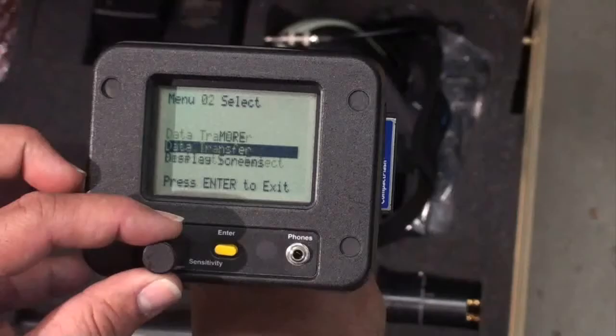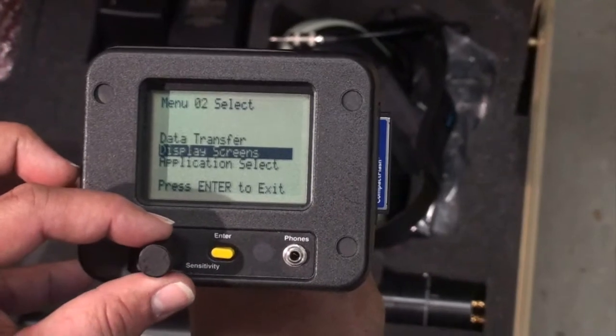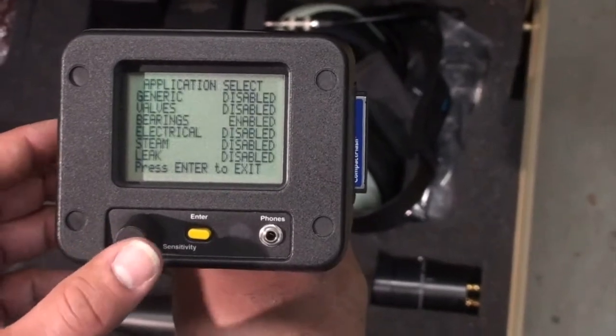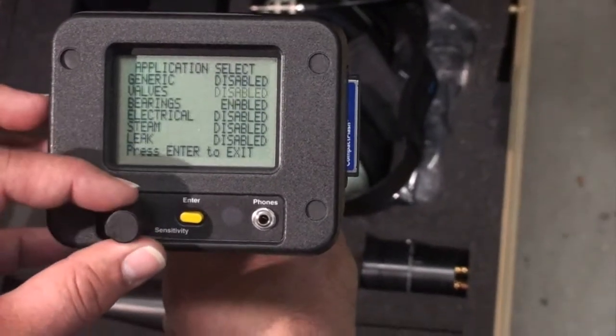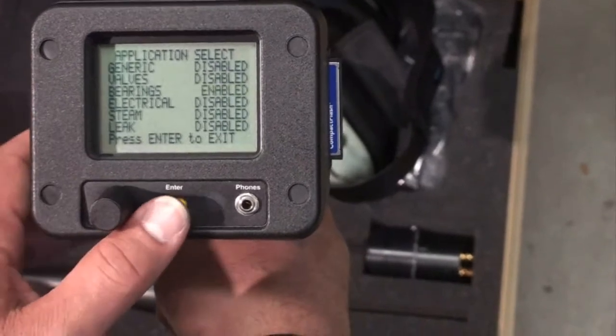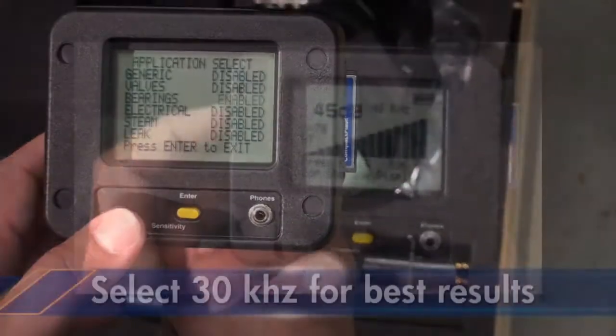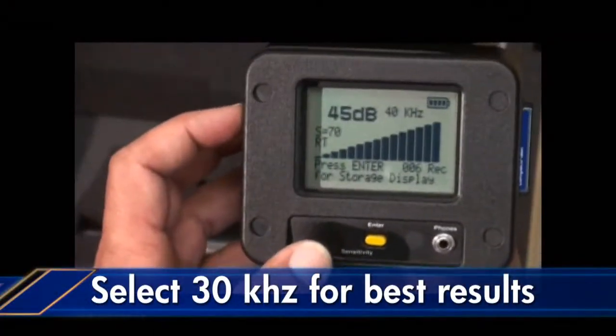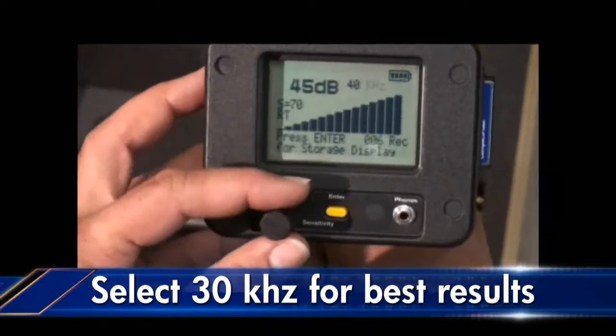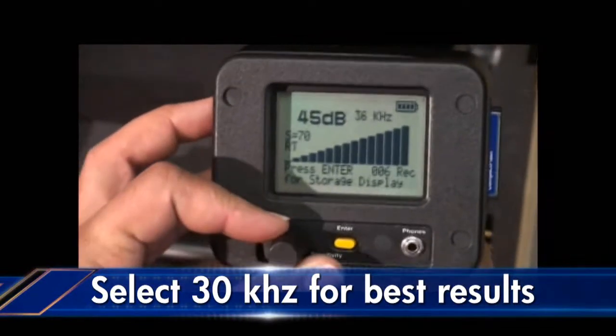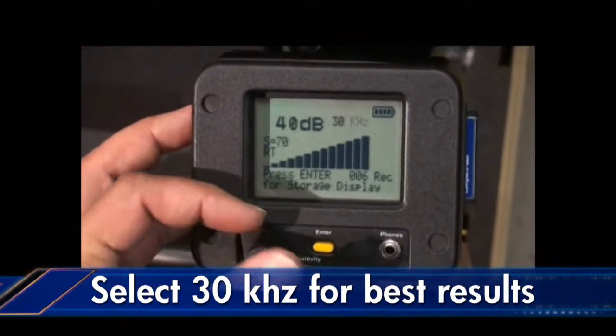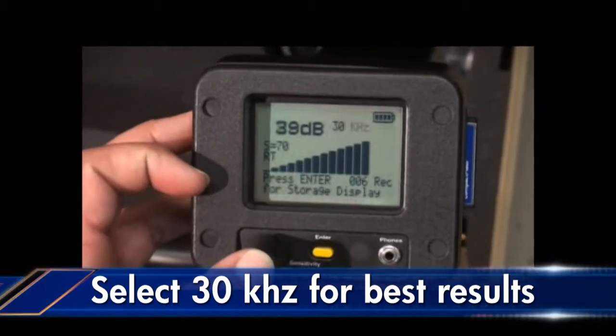First, open the application select menu and select the bearing application. Next, we'll use 30 kilohertz for best results when testing mechanical equipment. Here we're spinning down to 30 kilohertz and selecting it as demonstrated.